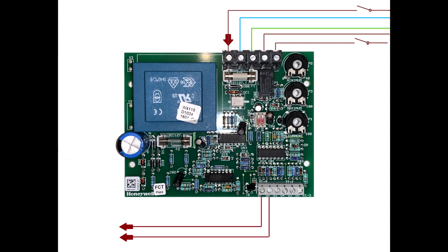That will control the gas valve's capacity, and this printed circuit board will take a signal from a programmable logic control, from a building management control, or from a special thermostat with the capability to supply 0 to 10 volts or 4 to 20 milliamps. So this printed circuit board has the capacity to control the gas valve actuator. Now these two wires on the right hand side, lower side, are the wires which will come from the building management control, from the programmable logic control, or from a thermostat that has the capability to supply 0 to 10 volts or 4 to 20 milliamps to this printed circuit board.